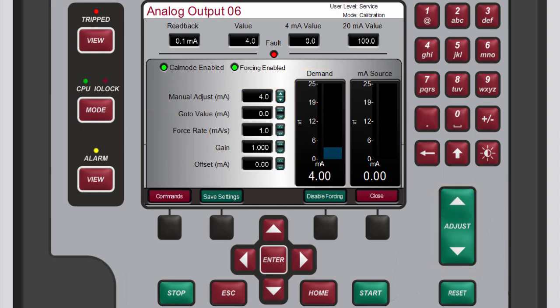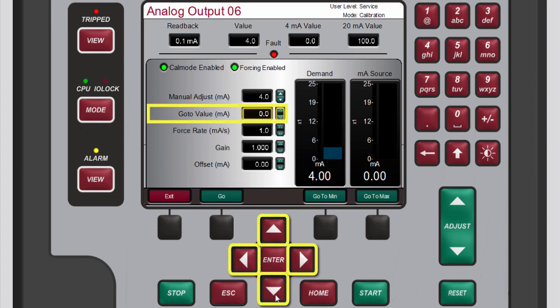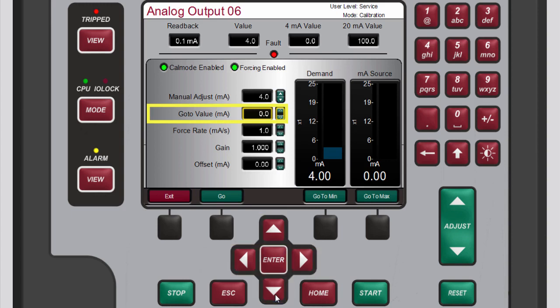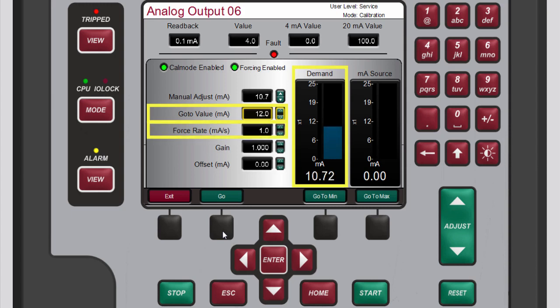You can also change the demand value by using go-to values. To do so, press the black function key below commands. A new set of buttons displays on the menu bar: go, go to minimum, and go to maximum. Use the navigation cross keys to highlight the go to value box. To change the current value in the go to value box, either use the adjust keys or press enter and use the numeric keypad. Then press the black function key below go. The demand gauge changes to the go to value at the rate defined by the value in the force rate box.